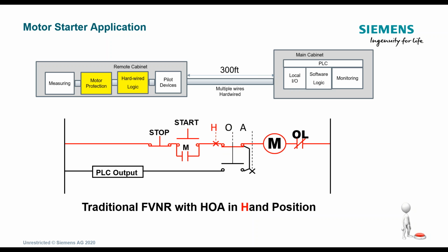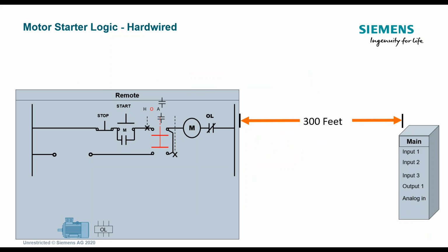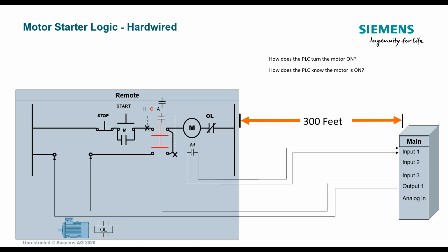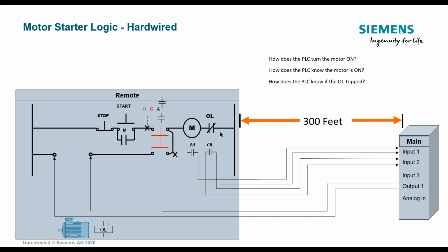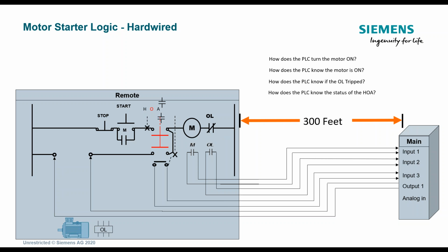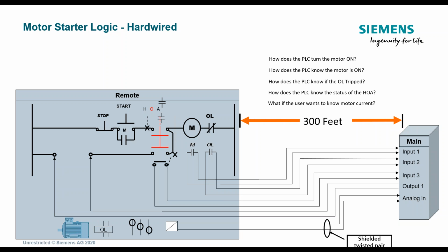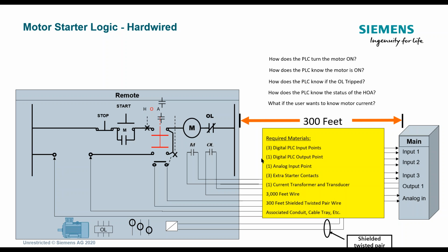Okay, hand in position, and then auto. So we build up a kind of hardwired logic, 300 feet, input, output cards, and so forth, and then maybe we want to have these contactors. Of course, we want a contactor stating that the motor is turning, it's pulled in, the 3-phase, and then you have an overload contactor letting you know that the motor's running okay, it's not in an overload state or heating. And then your HOA, so there's an auxiliary contactor there. And then if a customer or a plant requires monitoring current, then you're going to have a twisted pair going into an analog in. Okay, so 3 digital PLC input points, digital PLC output points. This is kind of the bill of materials, associated cable tray, conduit, and so forth.